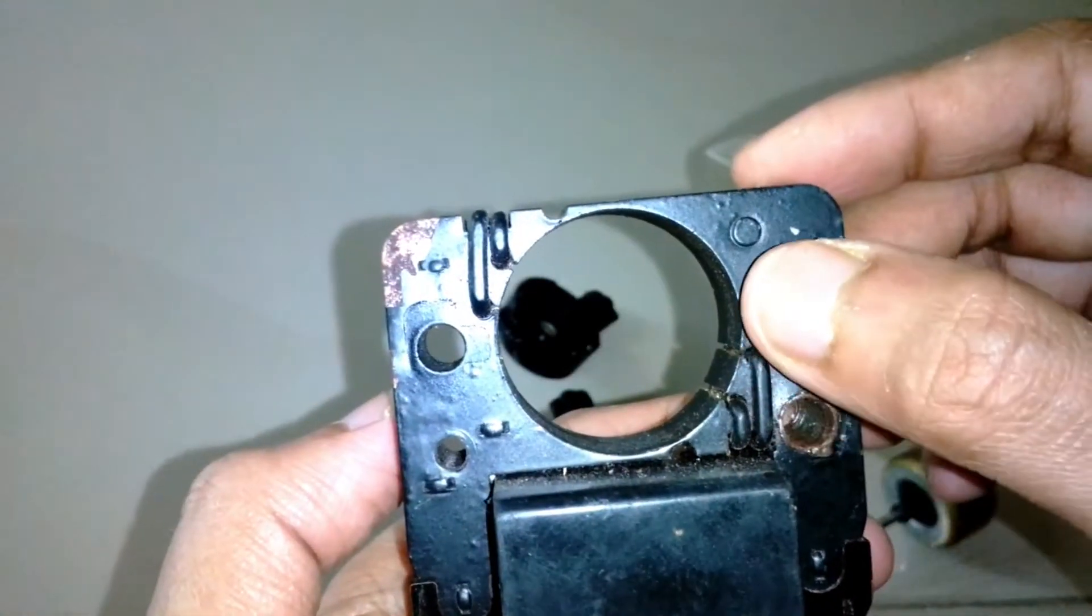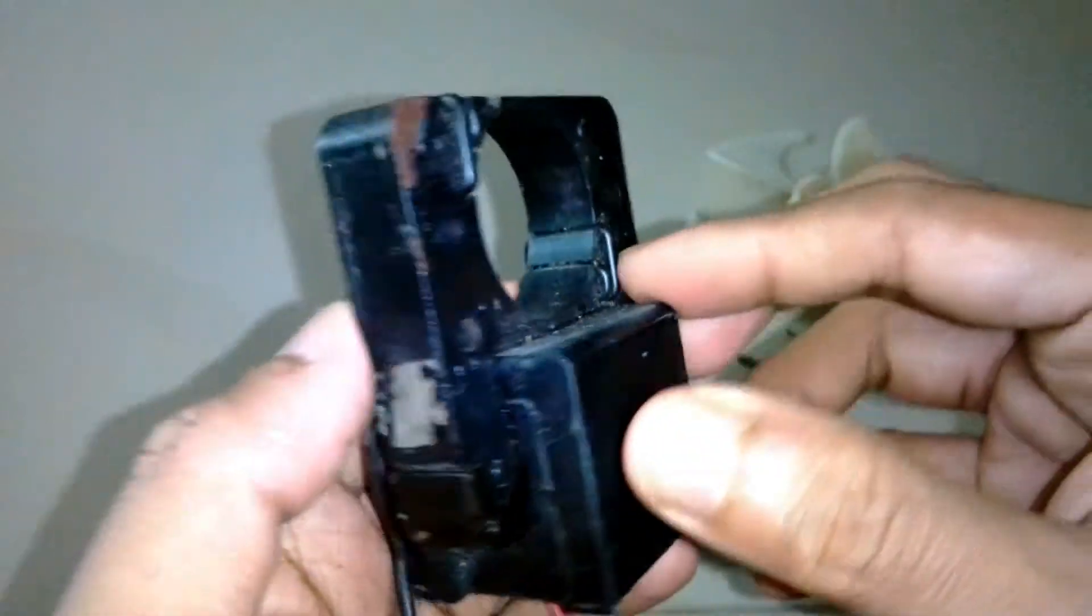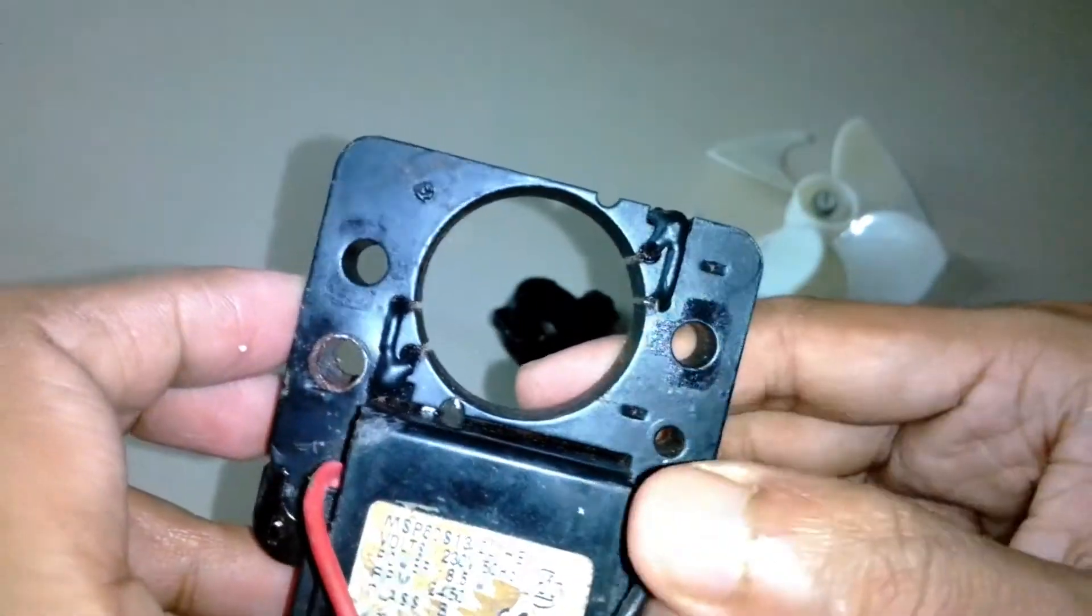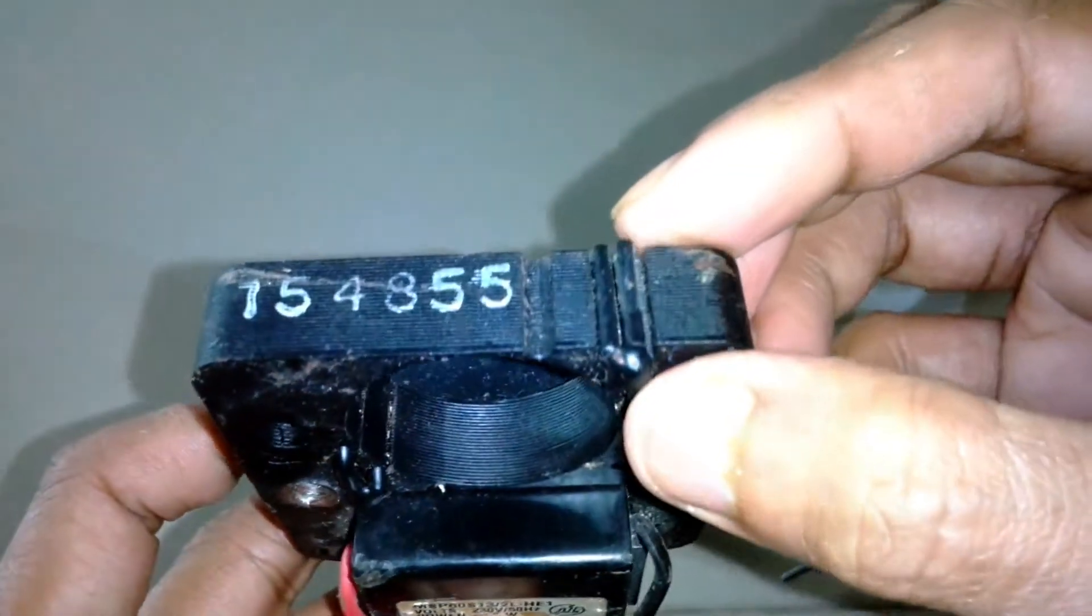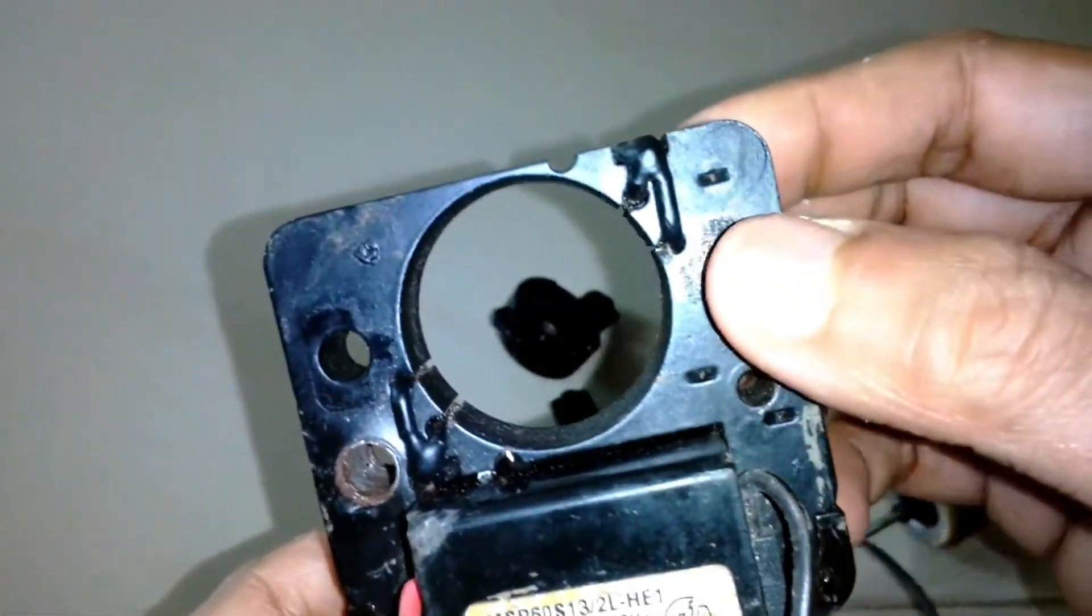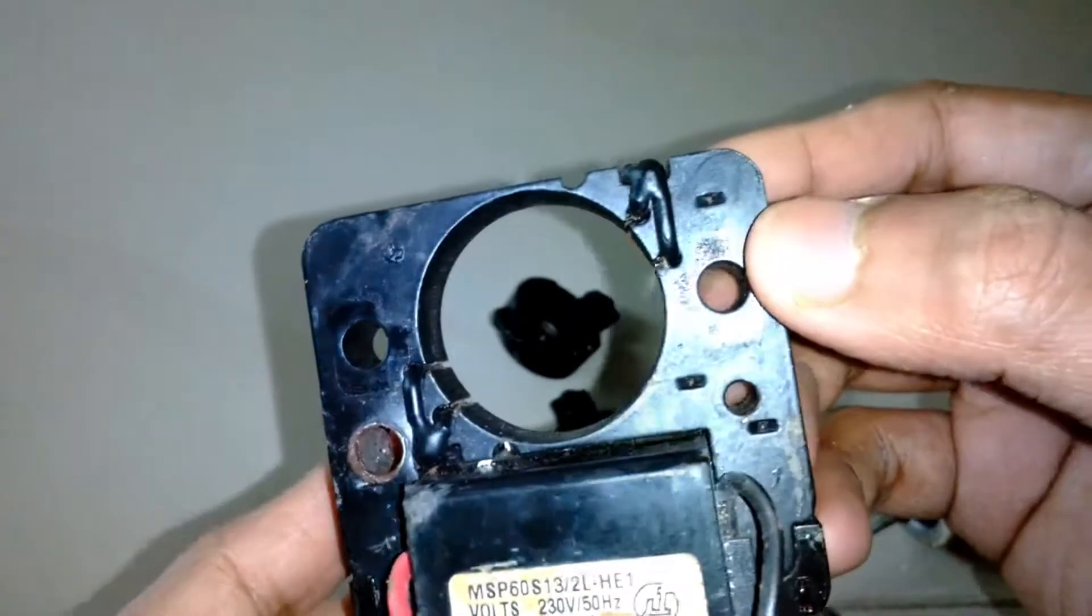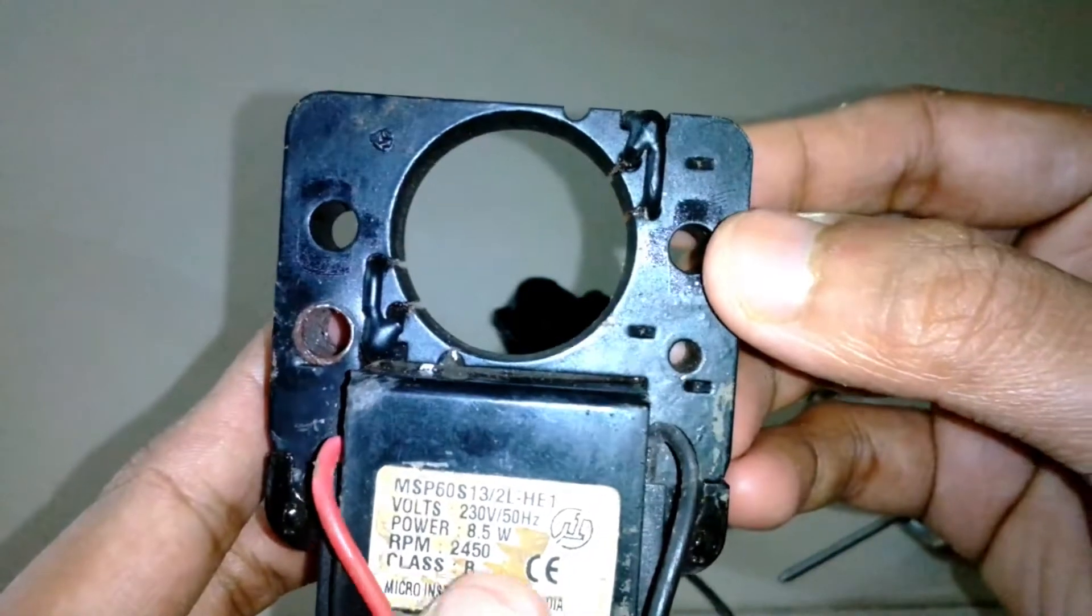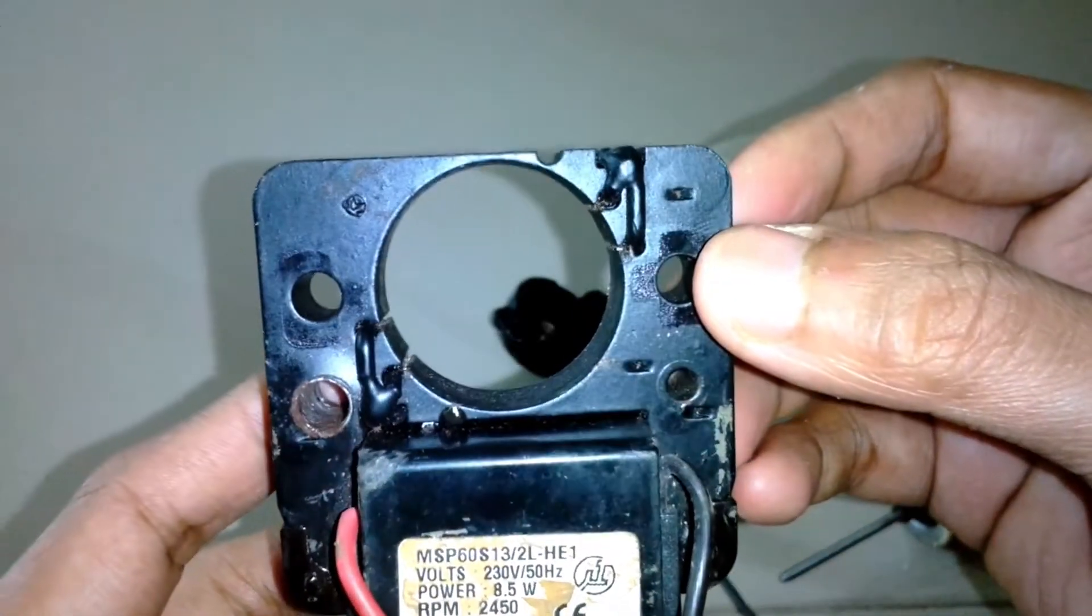As the magnetic field changes direction alternatively, these rings actually absorb some of the energy and redirect the magnetic field in such a way that the motor starts itself. Due to these rings, you cannot run the motor in reverse direction. That's one of the demerits.